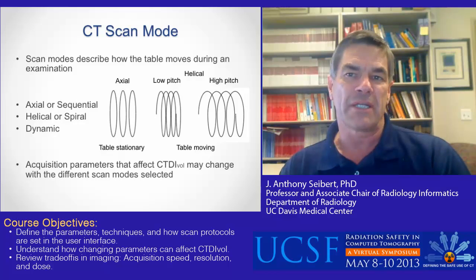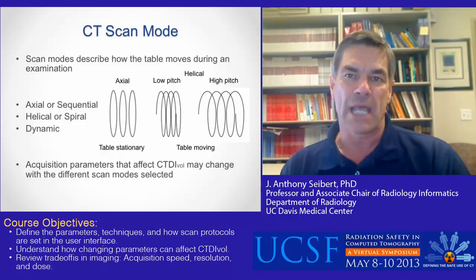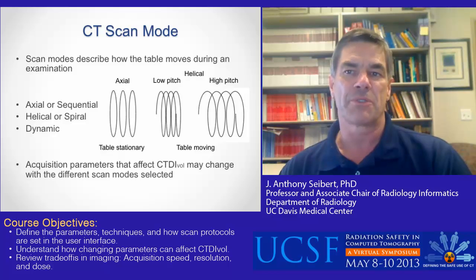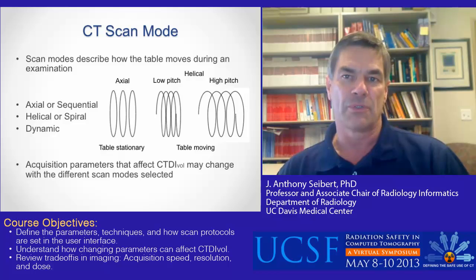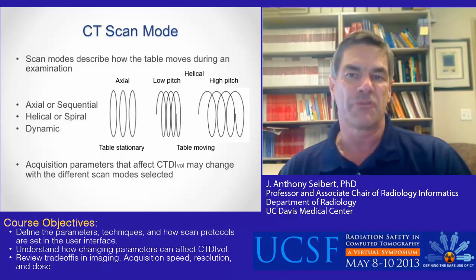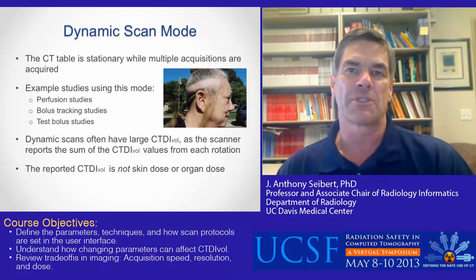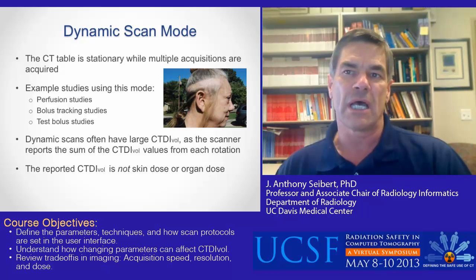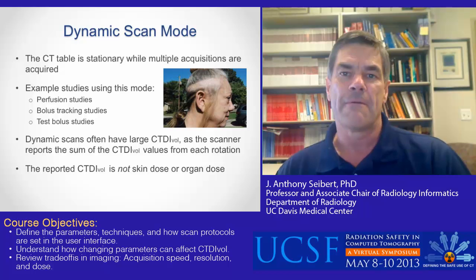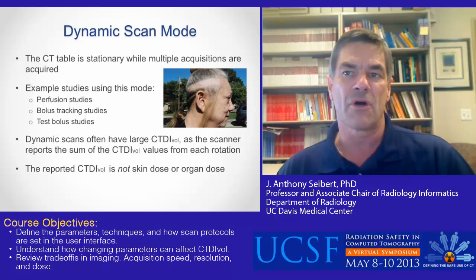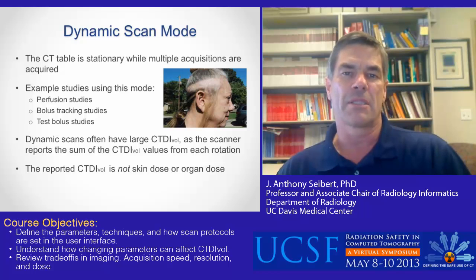The CT scan mode can be divided into three areas. Axial or sequential acquisition acquires data with the table stationary. Helical or spiral acquisition acquires image data with the table moving with respect to the collimated beam width. Dynamic acquisition acquires temporal image data at one position with the table stationary, but can be operated in a shuttle mode where the table quickly moves to a different position to image a different tissue volume and then moves back, repeating the scans over a period of time. Dynamic scan mode is used for perfusion, bolus tracking, and test bolus studies. Because the tube can be operated in the same position over an extended time, high radiation dose can be delivered, as exemplified by the hair loss of a patient undergoing a CT perfusion of the head. The CTDI vol is often reported as the sum of the CTDI vol from each rotation, and it is important not to assume that the CTDI vol is the skin or organ dose, which can be smaller or larger depending upon the particulars of the study.